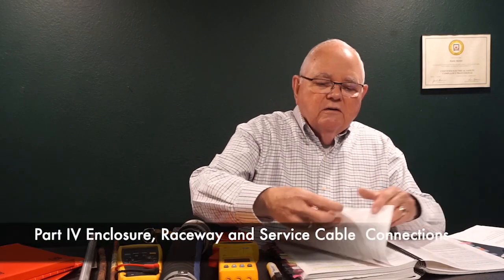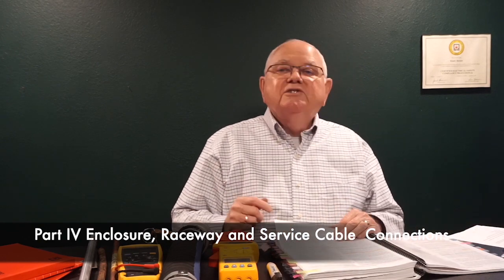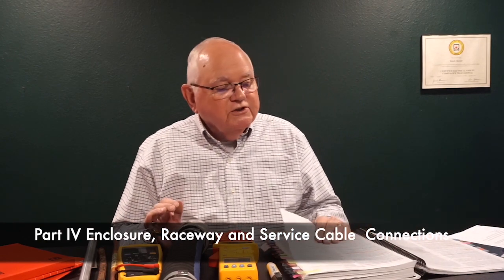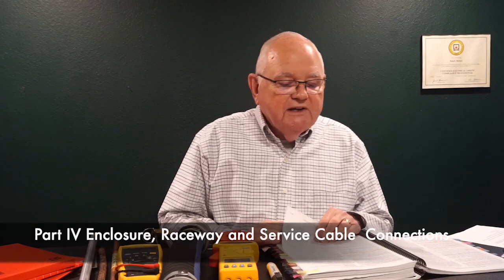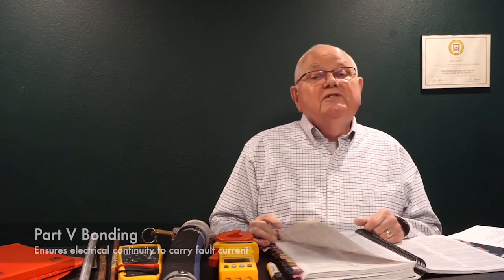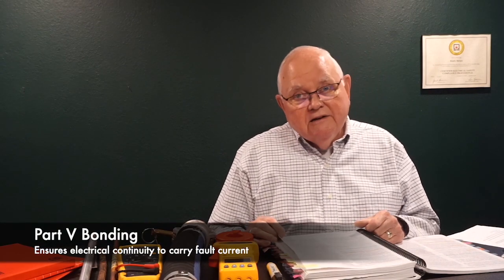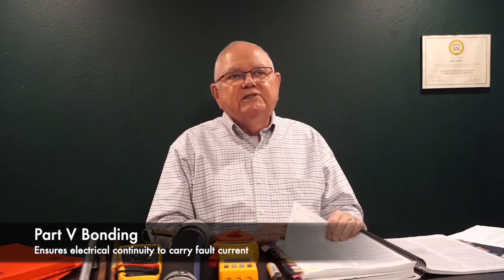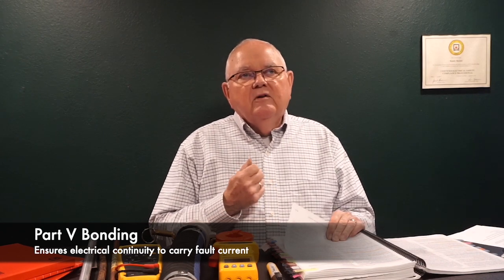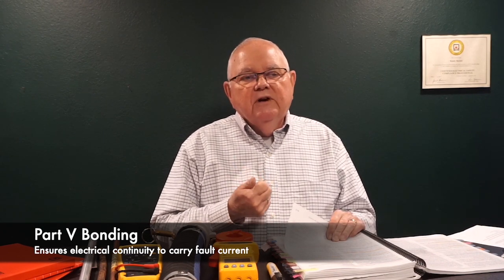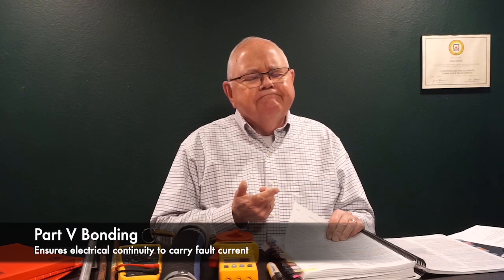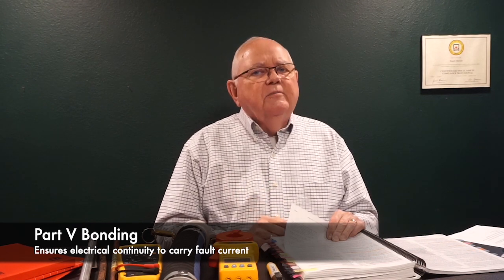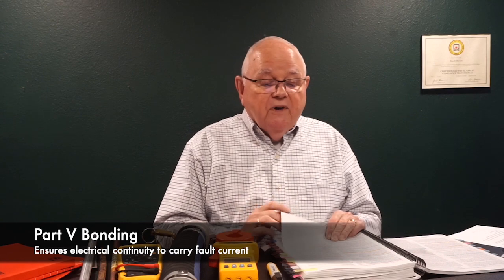Part four is a fairly short section. Part four of Article 250, enclosure raceways and service cable connections. Part five is a big section, very important. Bonding. We just talked about why we bond. Let's see. If I don't clear the ground fault, the building can burn down or somebody could get electrocuted. I think part five is going to be pretty important to me. Okay? So part five is on bonding.